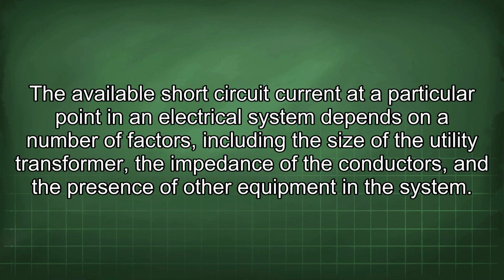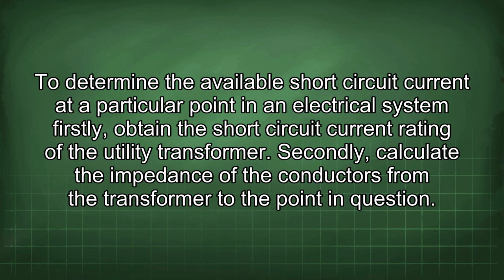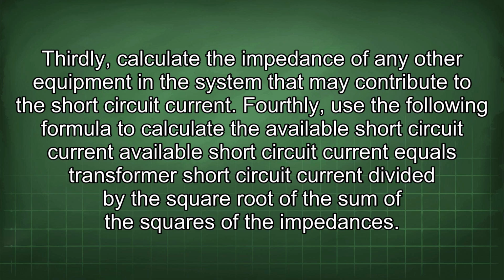The available short-circuit current at a particular point in an electrical system depends on a number of factors, including the size of the utility transformer, the impedance of the conductors, and the presence of other equipment in the system. To determine the available short-circuit current at a particular point in an electrical system, firstly, obtain the short-circuit current rating of the utility transformer. Secondly, calculate the impedance of the conductors from the transformer to the point in question. Thirdly, calculate the impedance of any other equipment in the system that may contribute to the short-circuit current. Fourthly, use the following formula to calculate the available short-circuit current.